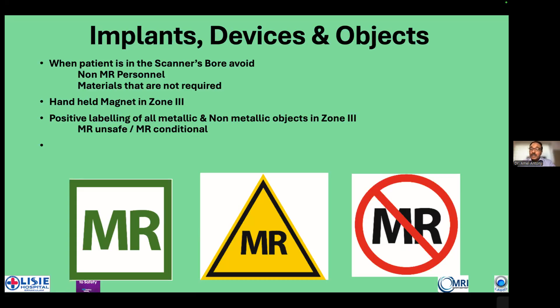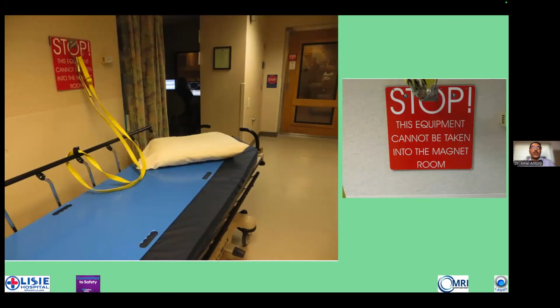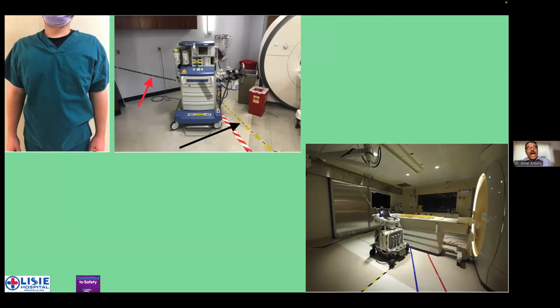A common thing which can go into the MRI suite is always a trolley. So that has to be mentioned clearly. Now you can see that this trolley is strapped to the wall with a clear warning that this trolley should not be taken into the MRI room. And even the supporting equipment like MR ventilators and MR pressure injectors are safe only to a certain distance, because the magnet has gauss lines, and there are certain gauss lines beyond which the machine should not cross. If it crosses, even these so-called MR safe ventilators and other equipment could be pulled into the magnet.